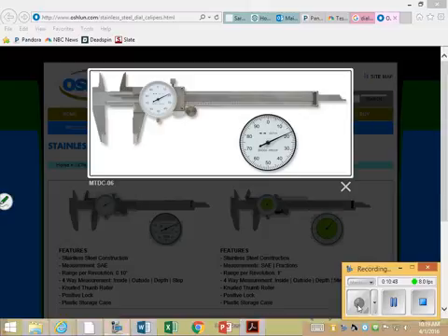To do that, you're going to use what's called a dial caliper, which looks exactly like this. What you do is you use what's called the thumb screw here, and turn that thumb screw until it pinches the wire between these two jaws. This little indicator will wheel around, indicating how many thousandths of inches there are between the two jaws. Notice this is 100, but since each one of them is a thousandth, when this needle goes around once, that's 100 thousandths of an inch, which is to say 1/10 of an inch.